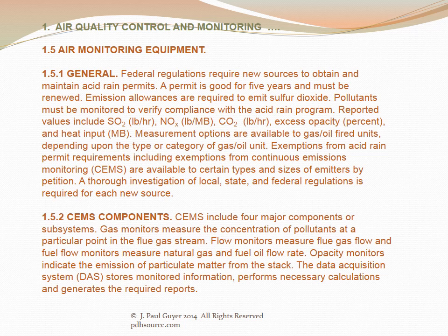CEMS components include four major components or subsystems. Gas monitors measure the concentration of pollutants at a particular point in the flue gas stream. Flow monitors measure flue gas flow, and fuel flow monitors measure natural gas and fuel oil flow rate. Opacity monitors indicate the emissions of particulate matter from the stack, and the data acquisition system, abbreviated DAS, stores monitored information, performs necessary calculations, and generates the required reports.